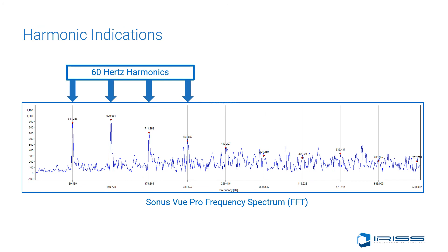The critical angle of electrical inspection is the angle at which the inspector records the best sound characteristics and decibel level of the anomaly. Sound analysis is critical in ultrasonic electrical inspection, and decibels can only be used to guide the inspector to the best angle to capture the sound wave. Decibels are only a reference to find this angle — not a measurement of severity — as they are not trendable for electrical inspection. Sometimes the incident wave travels away from the inspector's position and the critical angle cannot be achieved since the inspector is at an obtuse angle to the incident wave.